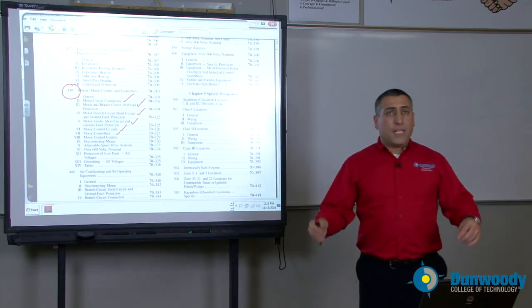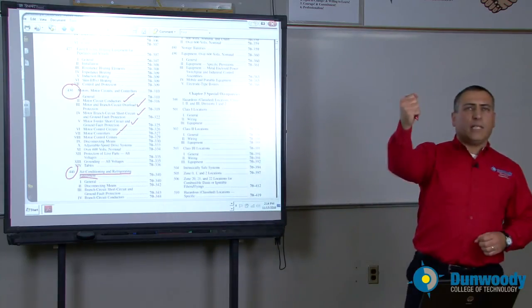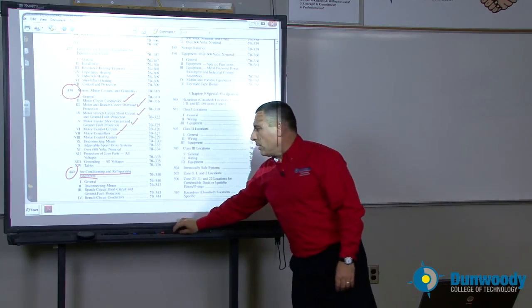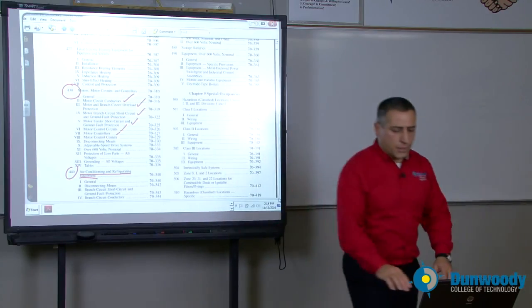If you're working with HVAC equipment — chillers, air conditioning — there's a whole article that talks about heating, cooling, and refrigeration equipment. In terms of where do I need a disconnect, what size conductor, what size overcurrent protection device — all this information you're going to find in article 440. Article 440, very important.